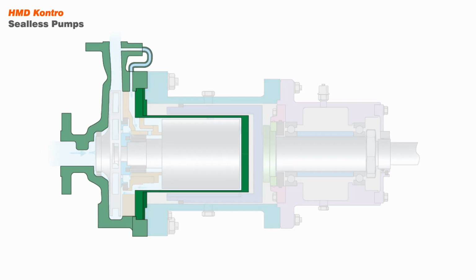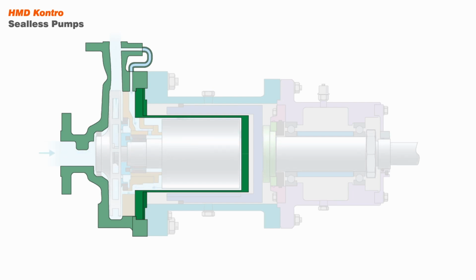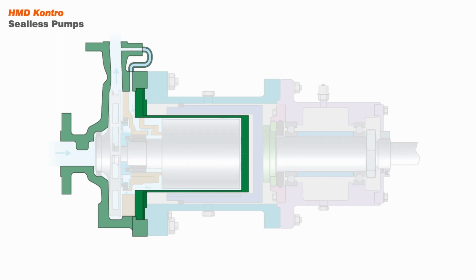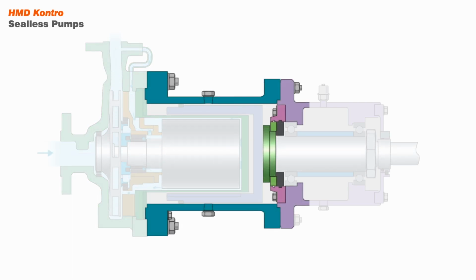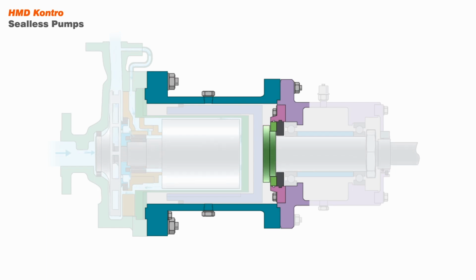It is important to explain the difference between the primary and secondary pressure boundaries of the magnetic drive pump. The primary pressure boundary comprises the pump casing, generally a thick-walled cast component sealing the process to atmosphere, and a thin-walled containment shell between the two parts of the magnetic coupling. The containment shell is located inside the magnet coupling housing, which may, as a design option, be sealed to form a secondary pressure boundary. A dry-running mechanical seal between the rotating shaft and the static coupling housing completes the sealing of the secondary pressure boundary.